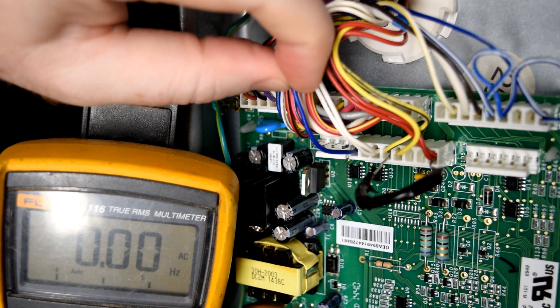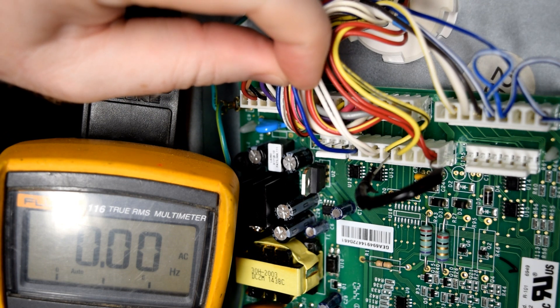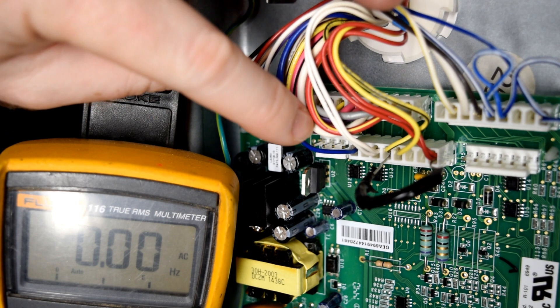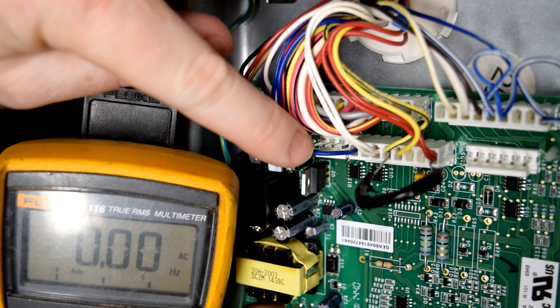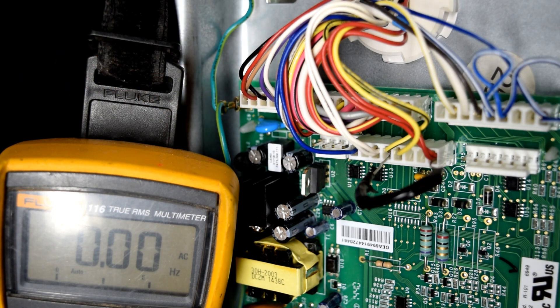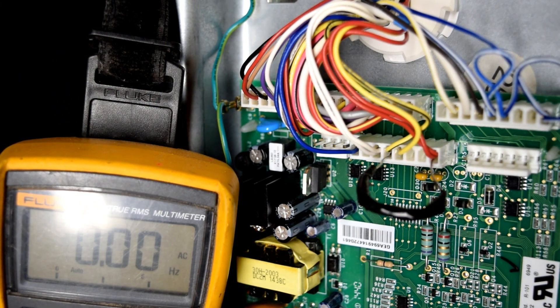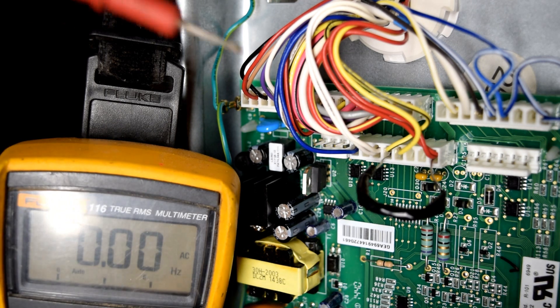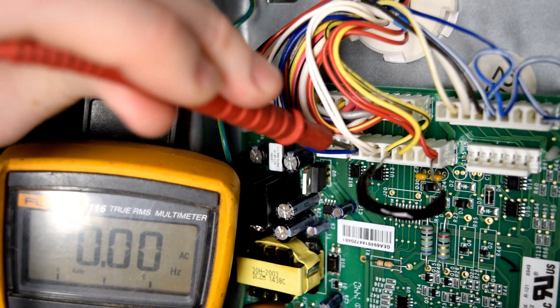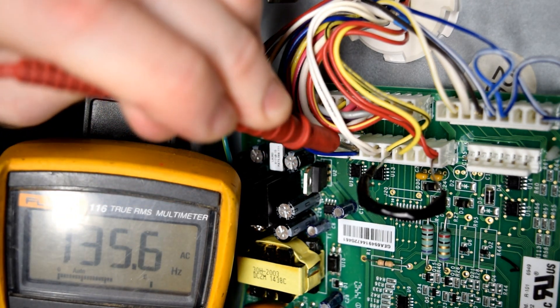It sends a frequency back to the control board through this blue wire. And we're going to measure the Hertz frequency on that blue wire. So if your meter has a Hz setting, that's the frequency response from that tachometer.